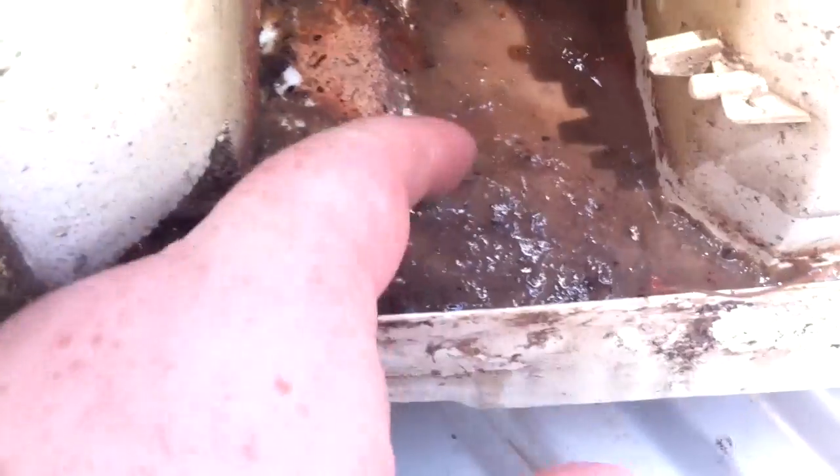The panel's off, and there is some pretty good sludge in there — looks like maybe even some dirt. It's kind of viscous, kind of like some sort of blob-like substance, but we're going to have to get all that out of there. Sludge — no wonder that slinger fan is not working very well. One thing we do have to watch out for is this electronic board.